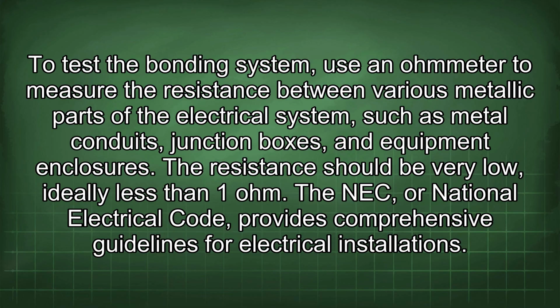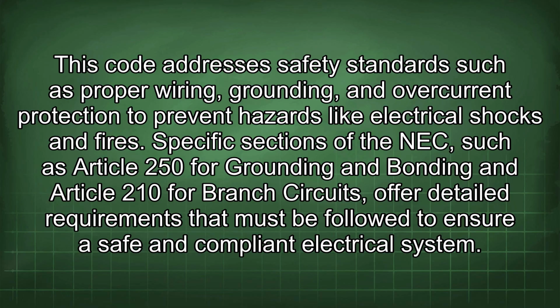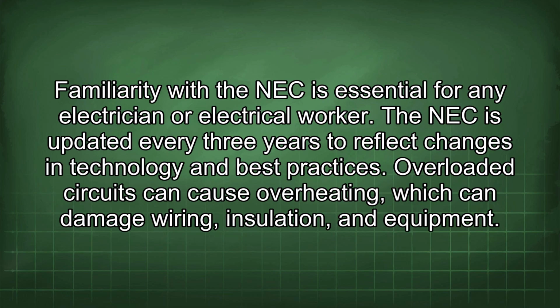The NEC, or National Electrical Code, provides comprehensive guidelines for electrical installations. This code addresses safety standards such as proper wiring, grounding, and overcurrent protection to prevent hazards like electrical shocks and fires. Specific sections of the NEC, such as Article 250 for grounding and bonding and Article 210 for branch circuits, offer detailed requirements that must be followed to ensure a safe and compliant electrical system. Familiarity with the NEC is essential for any electrician or electrical worker. The NEC is updated every 3 years to reflect changes in technology and best practices.